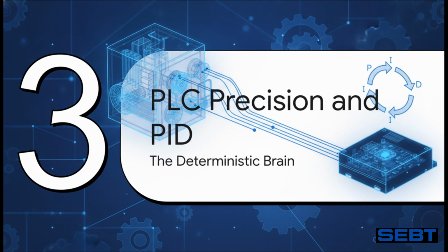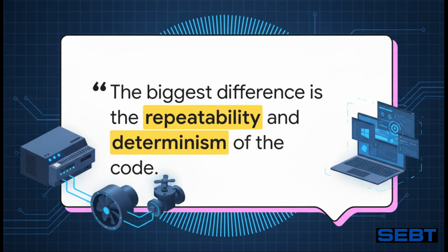Which brings us to Section 3, PLC precision and PID, the deterministic brain in the machine. I really want to highlight this fantastic quote from our sources here. Quote, "The biggest difference between an industrial PLC and a standard PC is the repeatability and determinism of the code." End quote. Guys, this is absolutely fundamental. Think about your standard laptop for a second. It might randomly pause what it's doing to run some annoying background update, right? You absolutely cannot have that happen when you're controlling heavy industrial fans and high-pressure valves. A PLC is deterministic. That basically means it makes a rigid promise that it will evaluate its logic in an exact, guaranteed time frame every single cycle without fail.